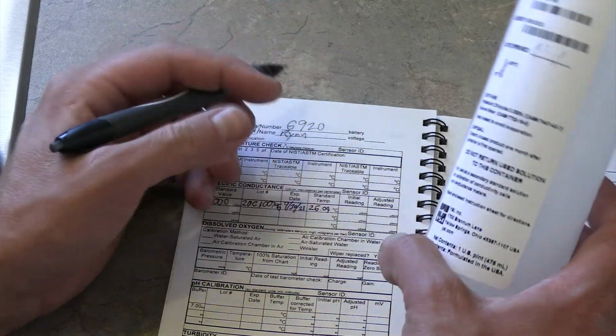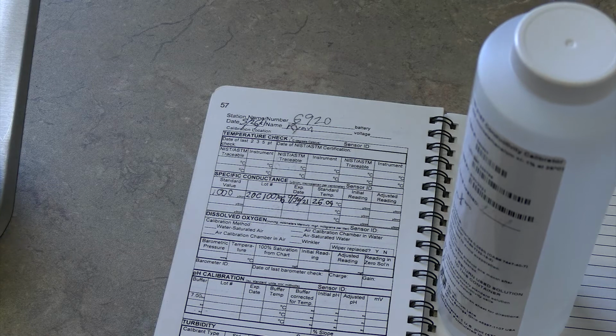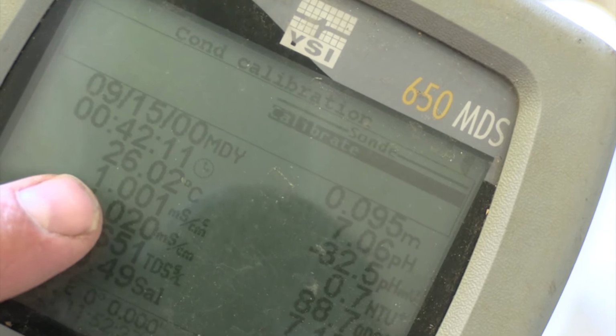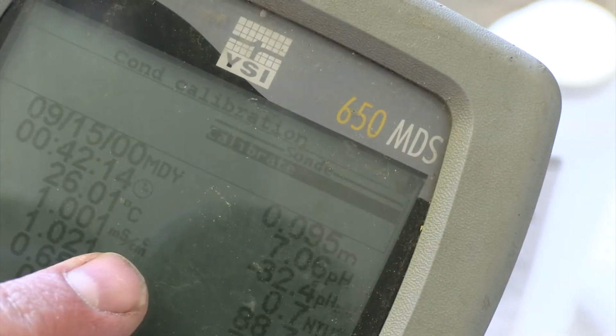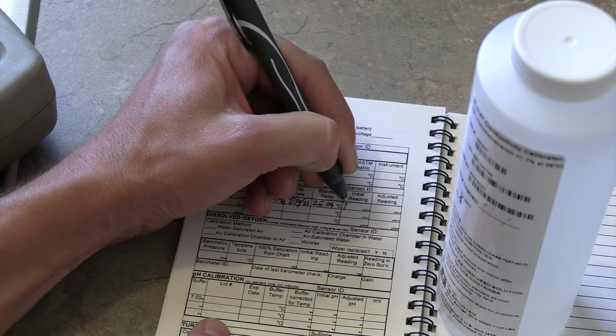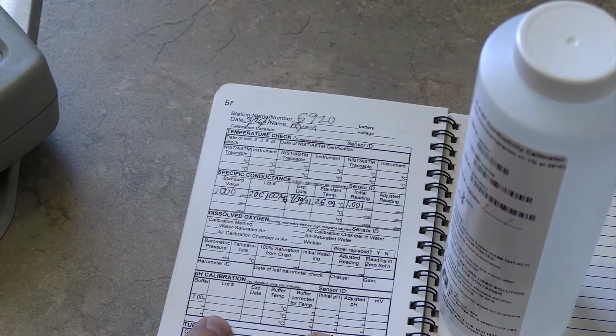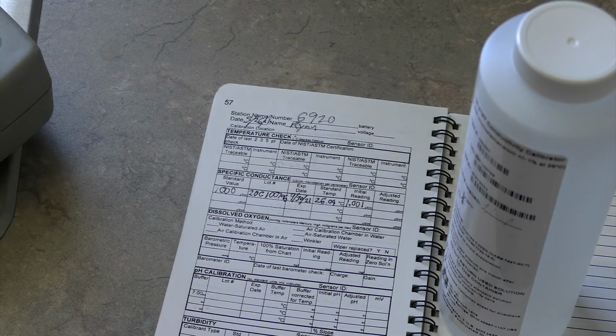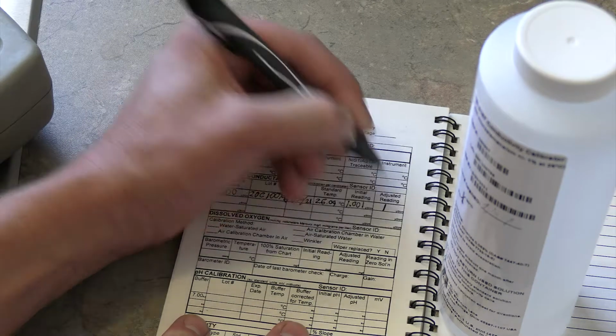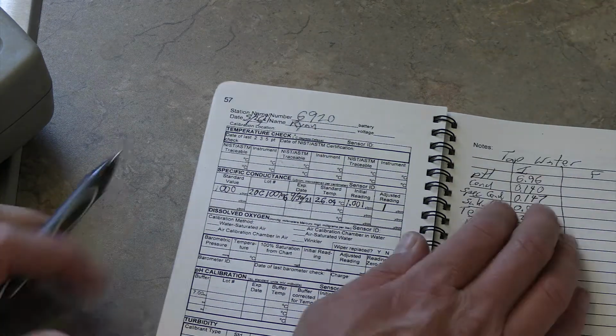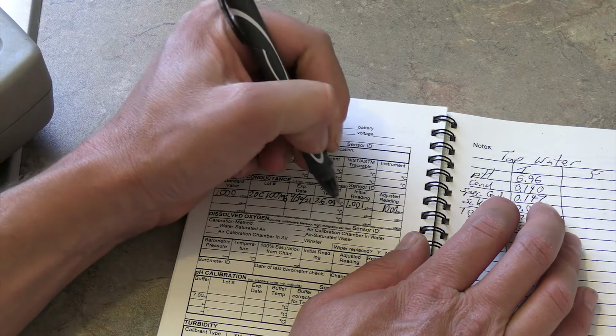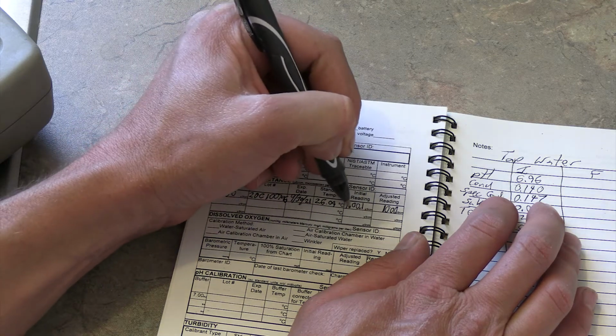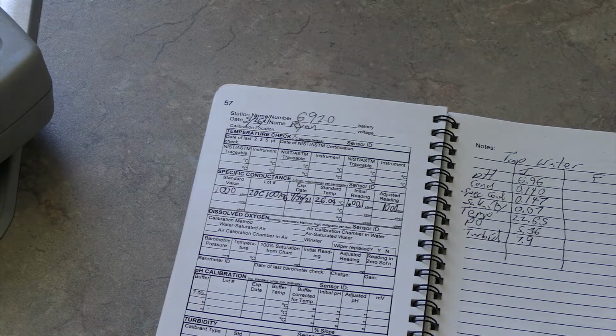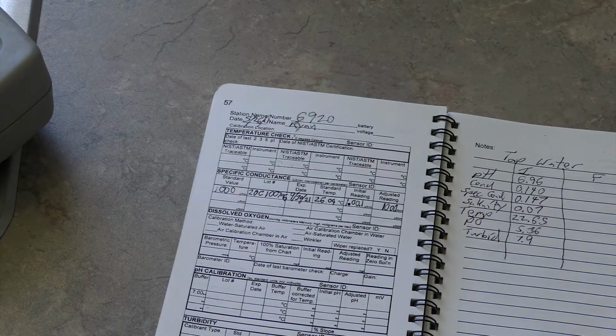And then our initial reading, let's look over here. Our initial reading is actually really close. This is specific conductivity on top, and it's actually 1.001. So that's great. It's actually not out of calibration. That's why I recommend doing this every 6 weeks or so, because sometimes it's just not out of calibration. And now I just put 1. So that actually does it. Or in this case, it's 1,000 because it's based around microsiemens. It's annoying, but that's how it works. Okay, so let's go on to the next one.